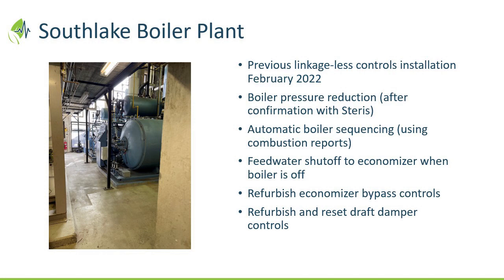Okay. Just to better understand linkageless controls. So for those that may not understand combustion, basically you got fuel, you got air. If you run your combustion mix with a little too much fuel, you run rich. So that means you can have fuel that's not combusted in your system. It can be dirty, it can be inefficient. If you go on the opposite side of that, you run too much air, you run lean. So now you're not utilizing all of the fuel you just spent a bunch of money on. And so what we always try and achieve is as close to perfect combustion as possible, right? That perfect gas and air mix.